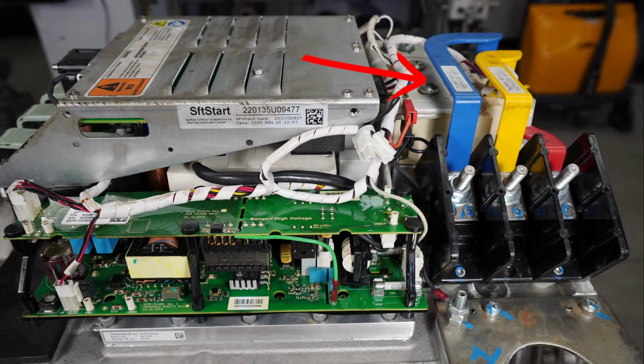And that shorted SCR then blows up half the system, because the fuses and everything did their job the first time and protected the rest of it, but the second time you weren't so fortunate, right? So that's why I say, if you have a main power failure like that, and this is true on any drive assembly, this isn't just a Turbocor thing, when this happens, verify your SCRs before you replace fuses and reset anything.